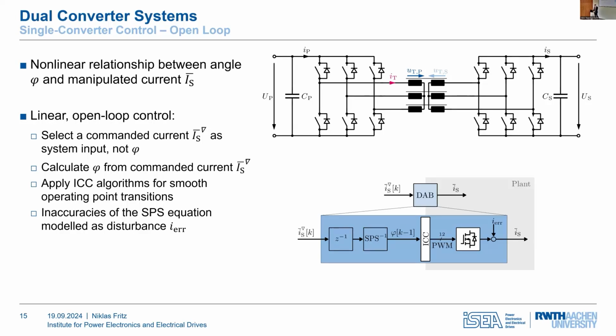Then you take an algorithm called ICC, or instantaneous current control, which was also developed at this institute about 10 years ago. This allows for this secondary side current to be established in a very dynamic way without generating a DC offset in the transformer windings.